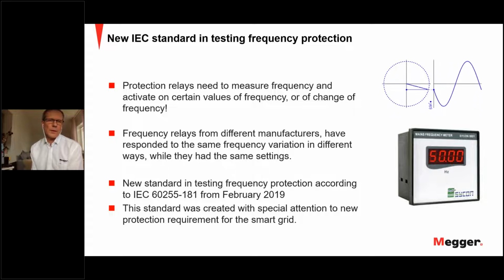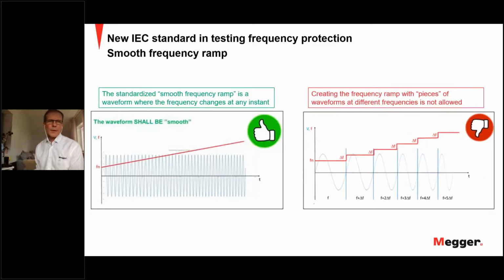So a new standard in testing frequency protection was made in February 2019. The standard was created with special attention to the new protection requirements from the smart grids. And the very important thing is to make a standardized smooth frequency ramp, a waveform where the frequency changes at any instant. It's not allowed to create a frequency ramp with pieces of waveforms at different frequencies.